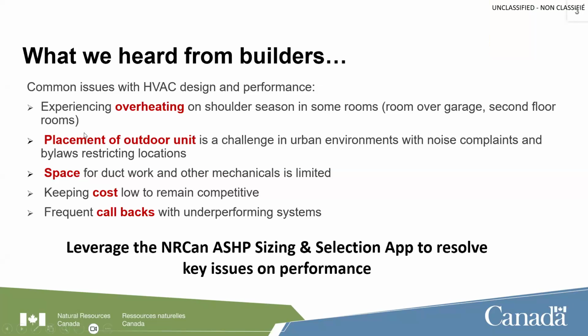Well, as we can see from the list here, we have a number of issues that we've experienced over several years. First off, overheating during the shoulder seasons on rooms on the second floor or rooms over the garage. There have been difficulties with placement of outdoor units, either against noise complaints or even local bylaws.